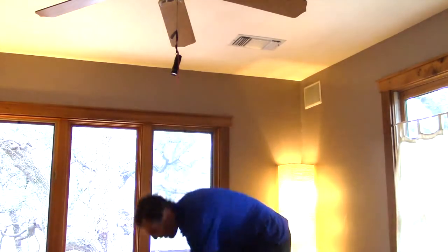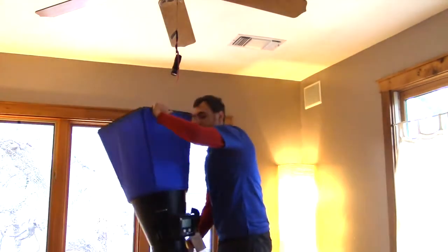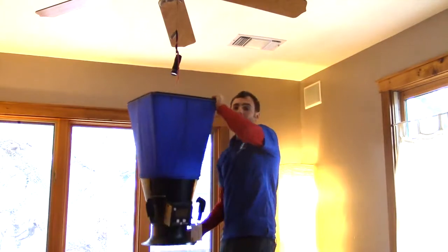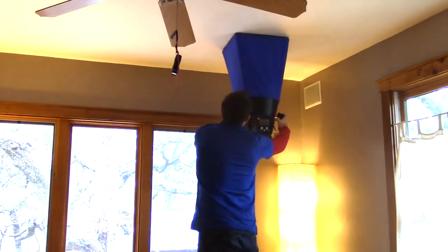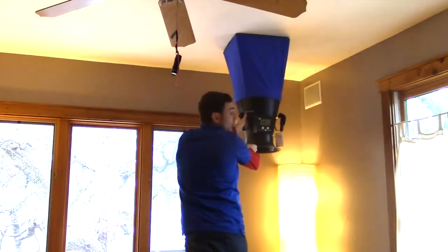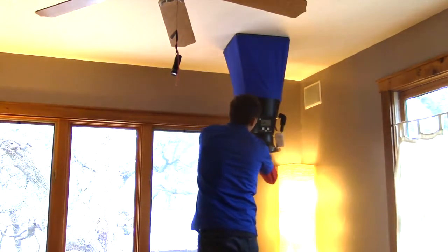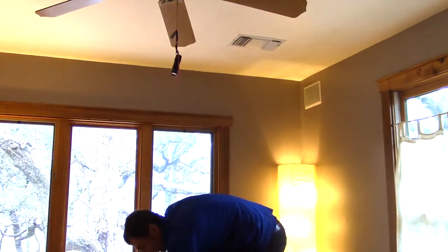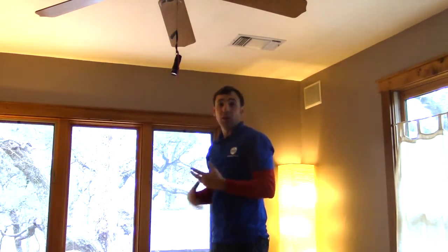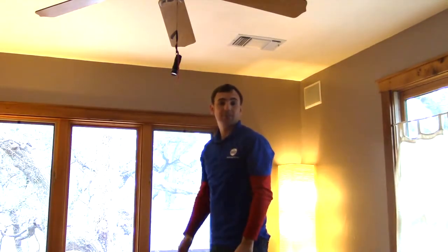So what I can do here is, this right here is an anemometer. This measures airflow. And I can measure the airflow in CFM coming out of the vent. So currently there's 115 CFM coming out of this vent. And I would then look at a manual J load calculation or some other load calculation that would show me the correct amount of airflow coming into this room so that I would know that the occupants are going to be comfortable with the amount of airflow coming out.